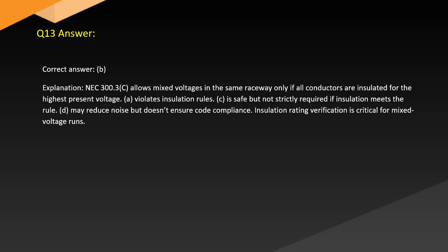Answer. Correct answer: B. Explanation. NEC 300.3(C) allows mixed voltages in the same raceway only if all conductors are insulated for the highest present voltage. A. Violates insulation rules. C. Is safe but not strictly required if insulation meets the rule. D. May reduce noise but doesn't ensure code compliance. Insulation rating verification is critical for mixed voltage runs.